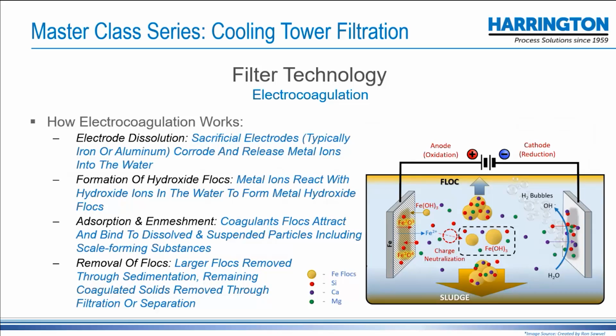But basically, you're causing a sludge to form, and there will be a lighter floc layer, which it will not remove, but that can be easily removed by post-filtration through a screen or a bag filter or a cartridge filter or even a media filter.